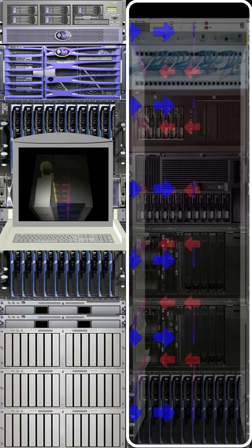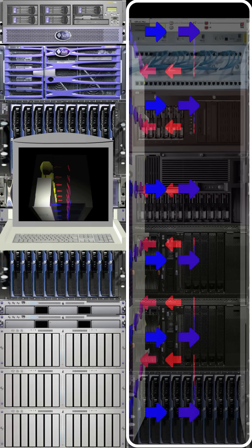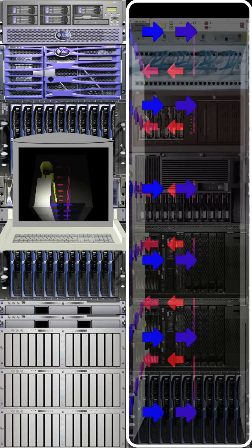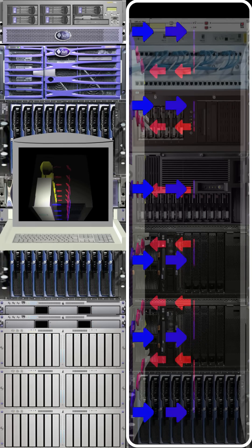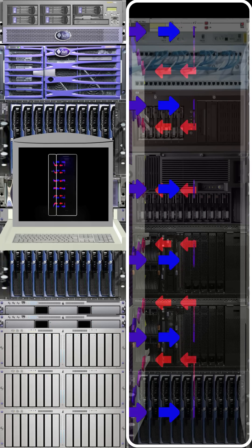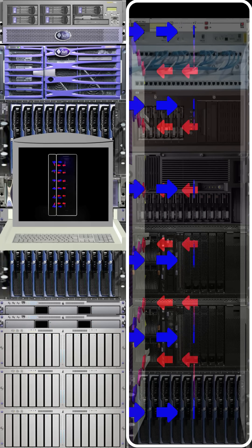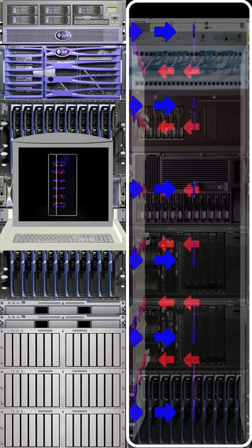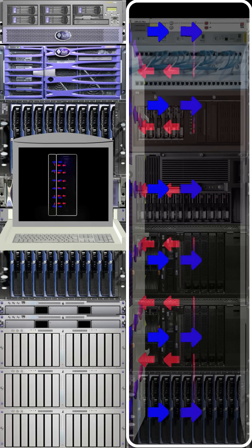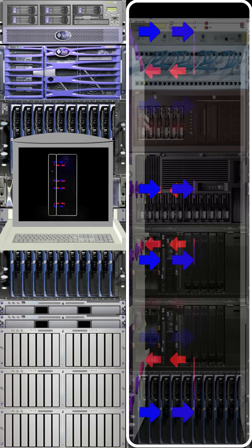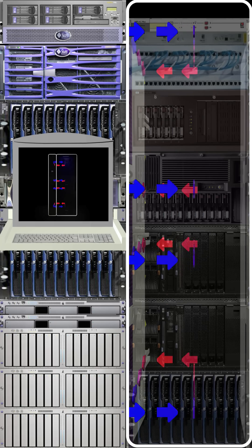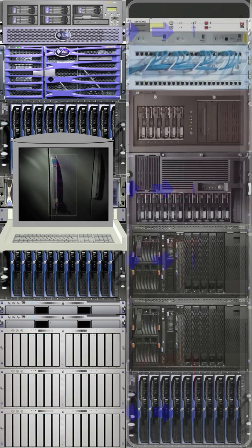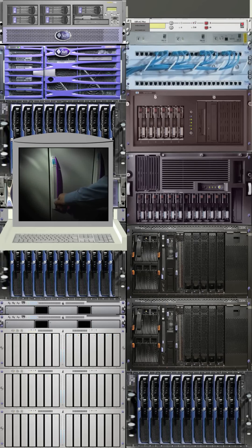The fans that push the air through the heat exchanger are fed from a single three-phase supply, two fans per phase. Therefore, in the event of a phase failure, two-thirds of the fans are still working. The remaining fans will automatically speed up to compensate for the two that have shut down.